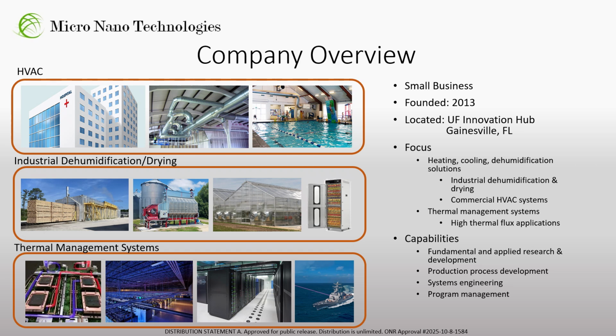As a result of this funding, MNT is currently field testing an atmospheric water capture system in a remote desert location and will start field testing two systems, one for an industrial lumber drying and one for a ventilation and air conditioning or HVAC application in late 2025. Working in collaboration with industry OEM partners, this field testing represents a significant step in the commercialization of this technology. Our cooling technology, experimentally shown to handle heat loads approaching 2,000 watts per square centimeter, can efficiently provide the cooling necessary for the next generation of chips, computers, data centers, and high heat load applications. MNT is working with several partners to field test this technology in high-performance data centers in early 2026.